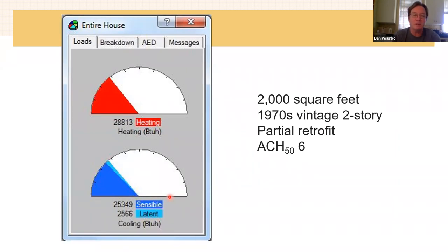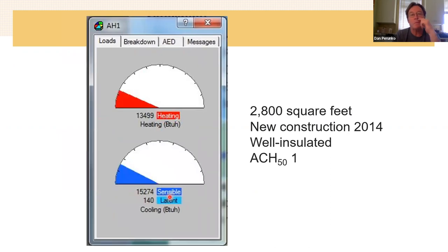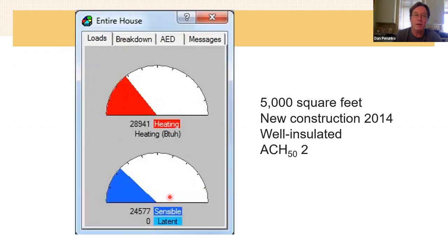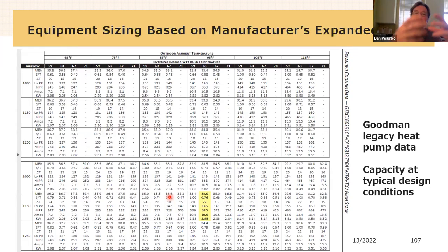So this is basically just over 2 tons of capacity. This is almost 3,000 square feet of house, and it's under a ton and a half. So really small system capacity. This is a huge house. It's 5,000 square feet, and it's just over 2 tons of required capacity. And you know this from doing a load calculation.